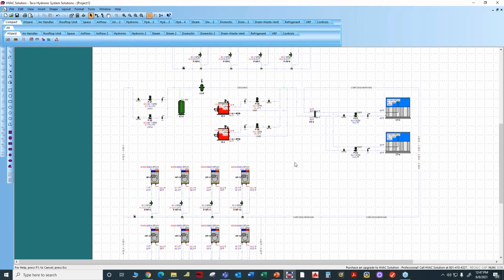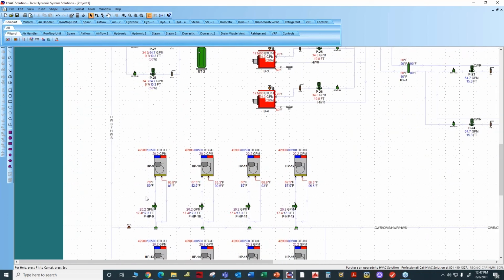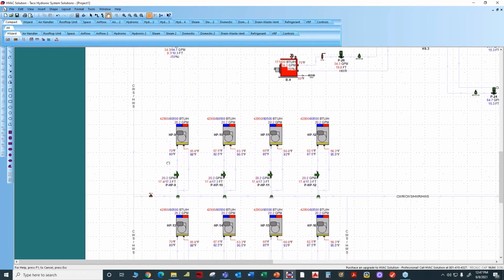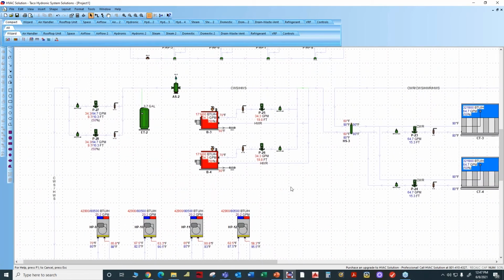So here we have the circulating loop, and the circulating loop wants to have a maximum temperature of about 80 degrees and about a minimum temperature of about 70 degrees. So we inject some hot water into the loop to maintain the minimum temperature of around 70 degrees, and then the cooling towers are used to maintain the maximum temperature at around 80 degrees.